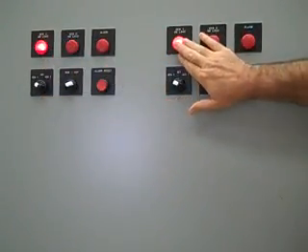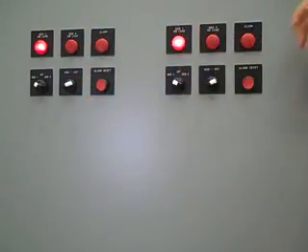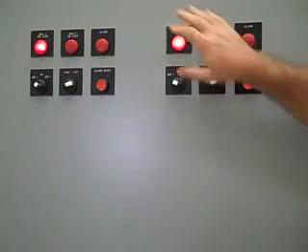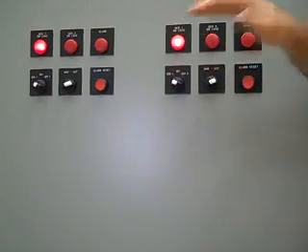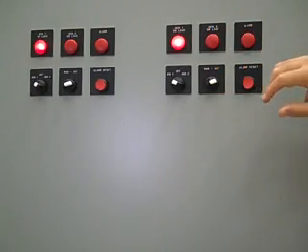And we know generator 1 is working because the switch is connected to generator 1. So it's telling us both transfer switches, switch 1 and switch 2, are connected to generator 1. Generator 1 happens to be the new generator, the single generator.